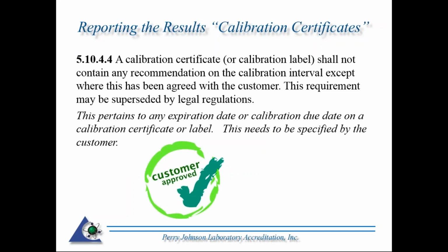Okay, continuing with calibration certificates and calibration labels. Shall not contain any recommendation on the calibration interval except where this has been agreed with the customer. This requirement may be superseded by legal regulations. So when you're a calibration lab and you're specifying a due date, an expiration date, that needs to come from your customer.